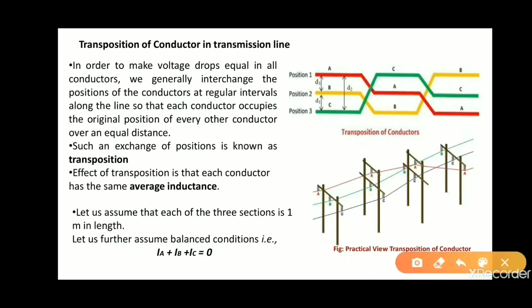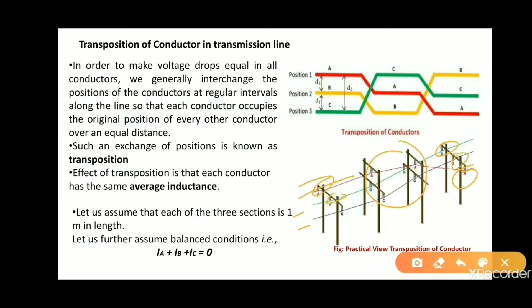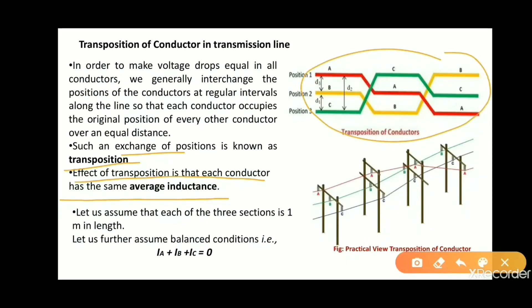In the practical view we can see conductor A, conductor B, conductor C — here is the transposition point, and after transposition conductor A, conductor C, and conductor B have exchanged positions. This exchange of positions is known as transposition. The effect of transposition is that each conductor has the same average inductance, so inductance will be equalized and all phases will be the same.